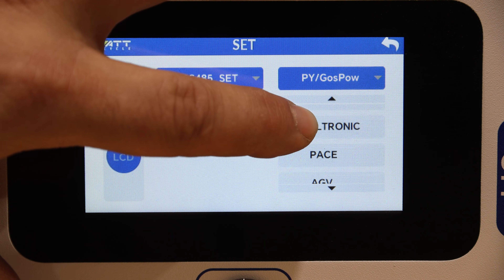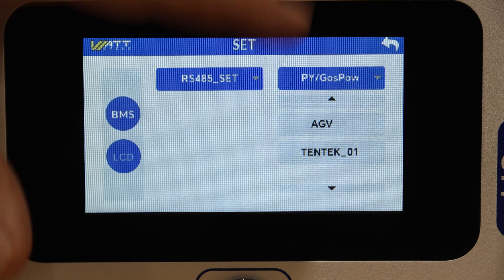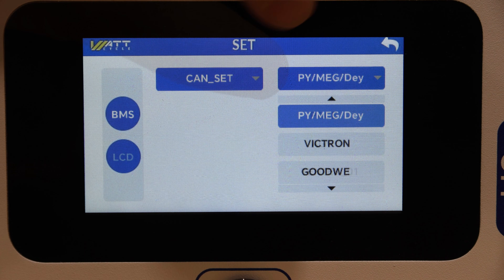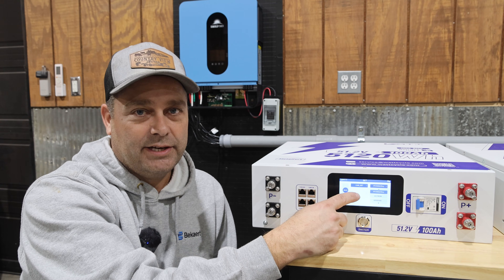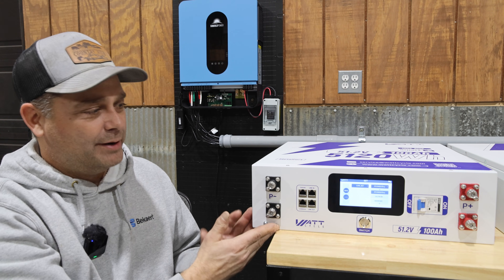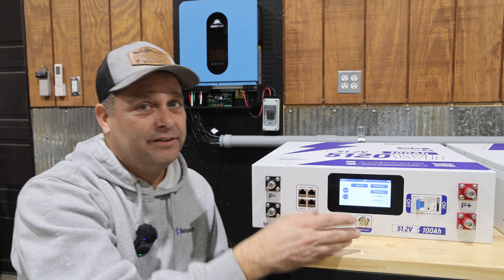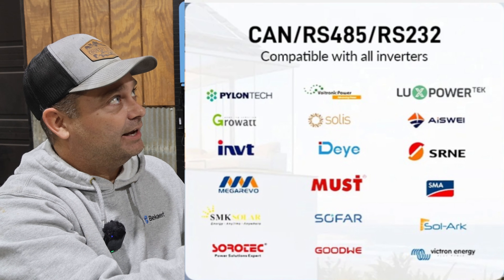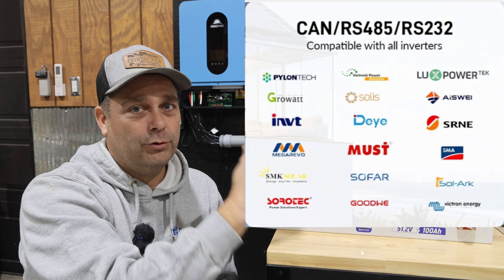You can also go over here and select RS-485 instead, where you have Pylon, Growatt, Voltronic, Pace, AGV, and TENTEK_01. I'm not sure what some of these are, so I'll go ahead and set it back to Pylon communication. This battery is supposed to communicate with up to 18 different brands — I'll put a graphic up from their website showing all of these brands that it should be able to communicate to through RS-485 or CAN bus.